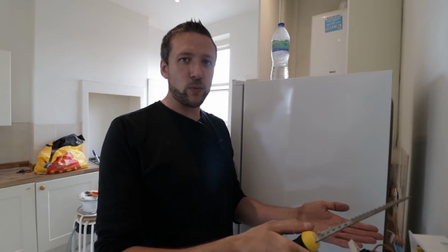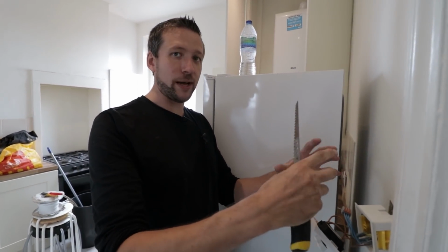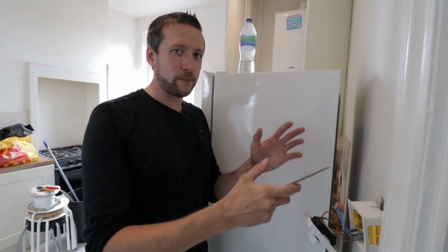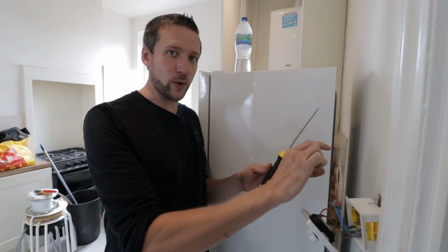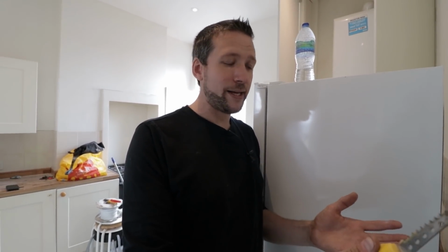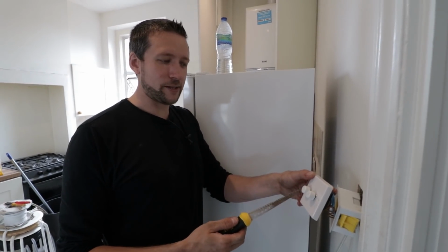Normally what you would do is put a double back box in and you'd have a 3-gang dimmer. But they have to be on a switch. So the only way around that is you either put an MK grid or something like that, and you have a grid and you put 2 dimmers and a switch. But wouldn't it be nice, like this customer who can't have MK in here, it's got to be Schneider. He wants all Schneider accessories everywhere. Now Schneider don't do that. I've been in loads of occasions where you want to have 2 dimmers and a light switch.